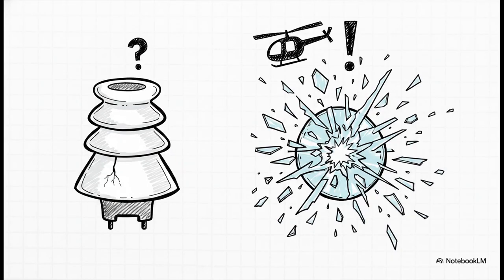But the real kicker here, the crucial point, is that glass actually has a hidden superpower when it fails. If a porcelain insulator takes a hit or gets overstressed, it might form a tiny, almost invisible microcrack that slowly degrades the system until it fails catastrophically. But glass? Glass completely shatters upon severe impact. Now, rather than a bug, this is a brilliant design feature. It means maintenance crews driving by or flying over in a helicopter can instantly spot a missing disc from the ground. They can find and fix failures rapidly, way before the whole grid goes down.